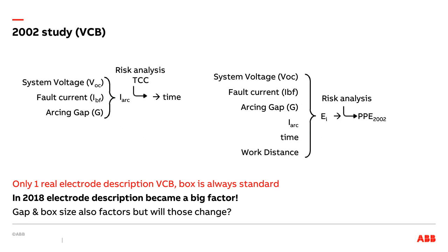If you look at a 2002 study, you look at the system voltage, fault current, arcing gap that develops the arcing current. You take that arcing current, you plot it on a time current curve that develops time. You may be doing some elements of risk analysis to figure out, well, can I trust that time current curve? Can I not trust it? Do I need to add tolerance? Am I using the right device? There is some risk analysis that probably should be done there.